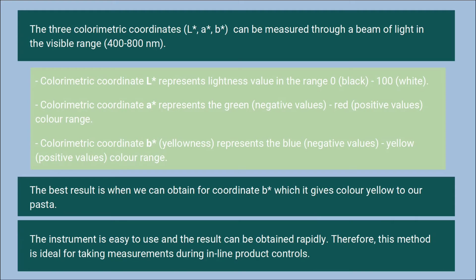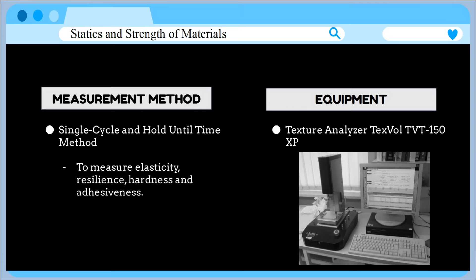For the last measurement method, the experiment can be done using equipment called Texture Analyzer TexVol TVT 150XP, which is assisted with a computer. By using this equipment, two types of test method can be done, which is firstly single cycle and secondly hold until time. From this method, we can measure elasticity, resilience, hardness, and adhesiveness.